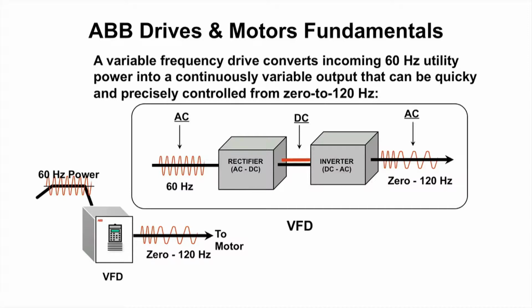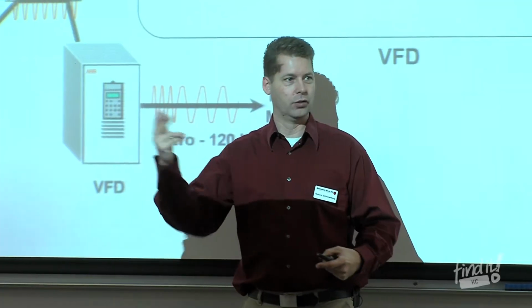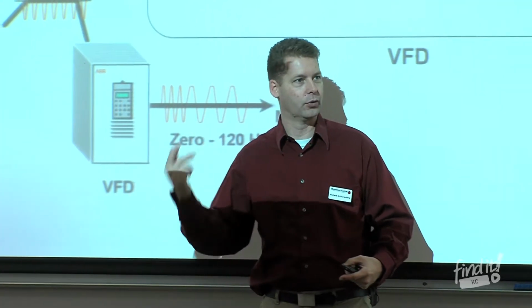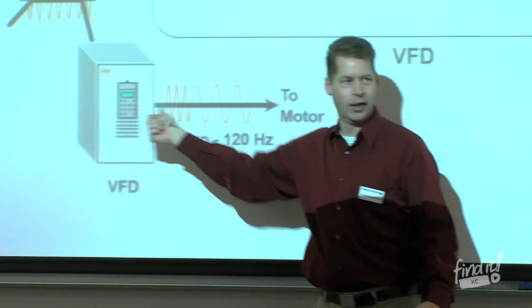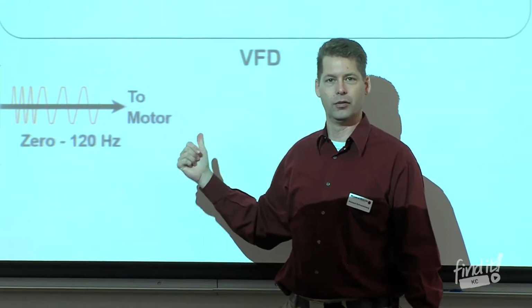Sometimes you have to choose a specific single-phase only incoming power VFD. All the ABB drives here that are rated for 208 volt 3-phase incoming power are also rated for single-phase operation. So you just omit one of the wires and you bring in two hot wires instead of 3 for running single-phase into the drive, and then it will always spit out 3-phase to a 3-phase motor.